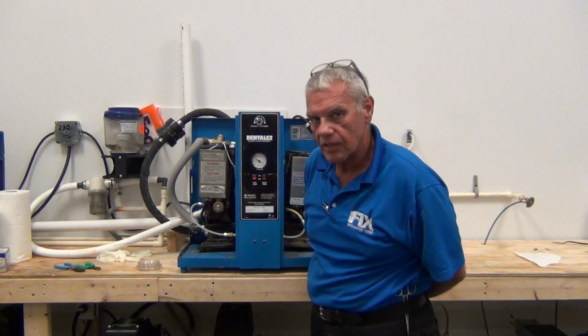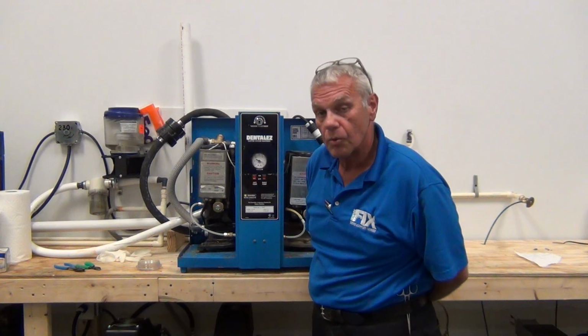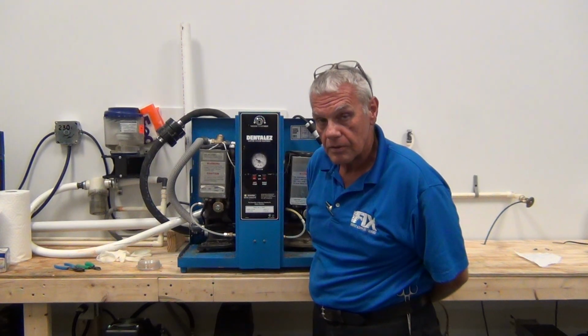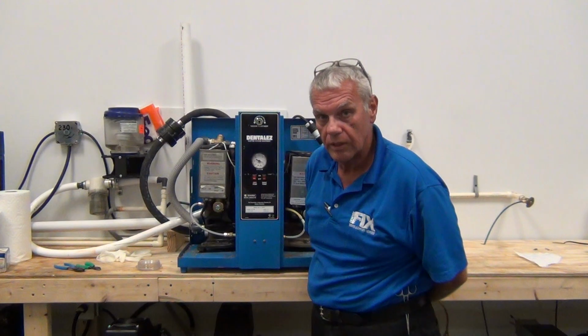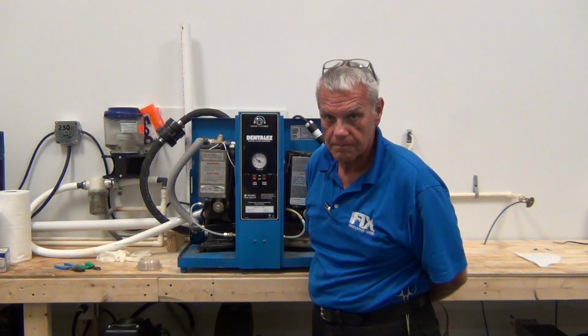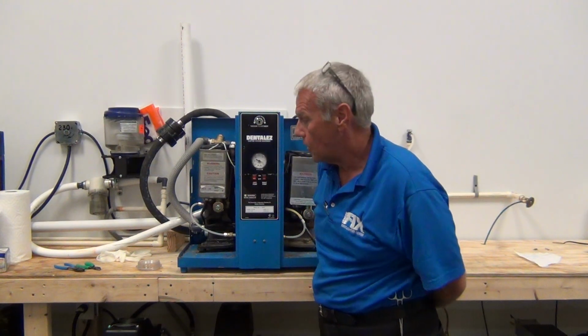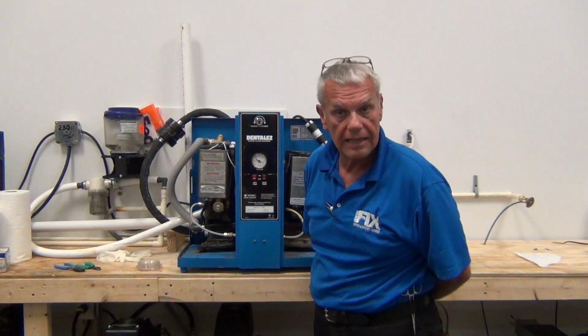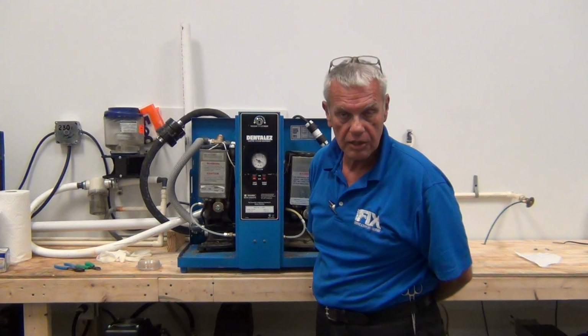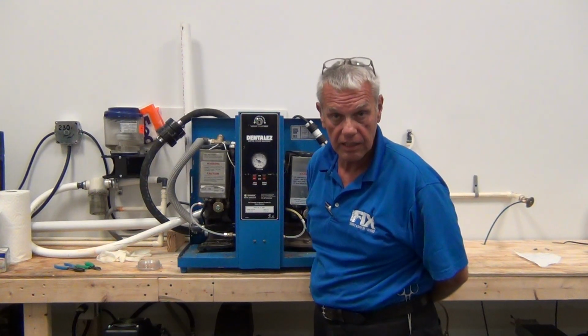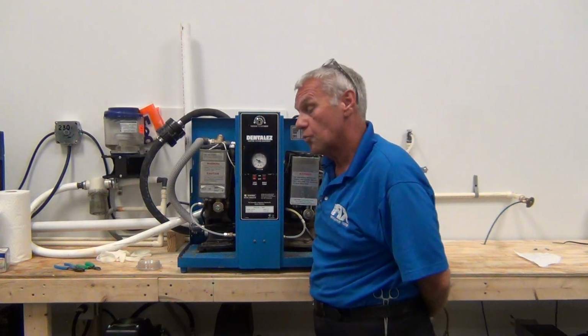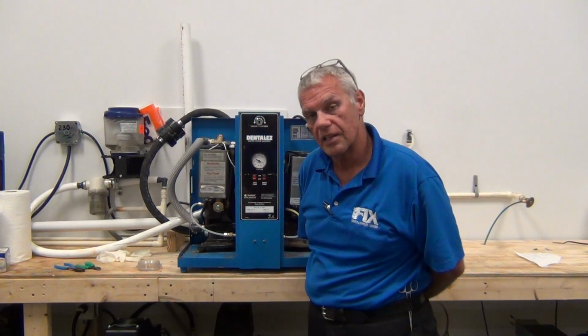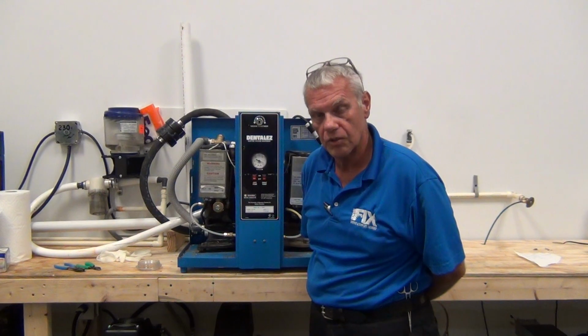Also, remember what I said earlier. Tell the doctor to run both pumps. Don't let them alternate week to week unless they're just dead set on it. It's best to run both pumps. It keeps them equilibrated, and it gives them maximum suction at chair side, the kind of suction they need for operative dentistry, as well as taking care of wear and tear on the vacuum pump. It equilibrates the wear and tear.